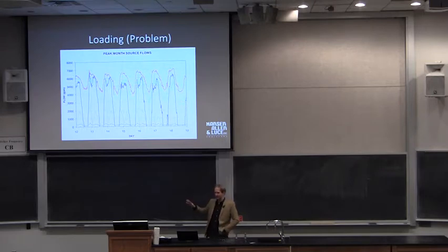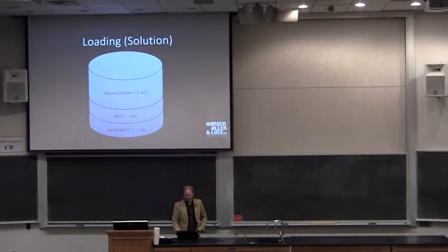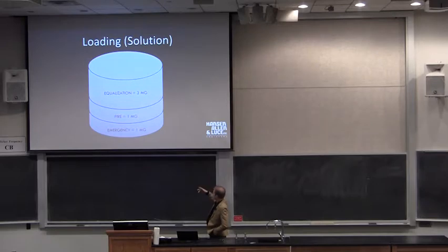So if you look around in the valley, you see lots of storage tanks, or anywhere that has water, there's usually a storage tank. Those storage tanks could be seen as batteries. If you think about it, water systems are one industry that has large batteries they can take advantage of. And so if this is a typical storage tank where you have your fire, you have your emergency storage, but most of the tank is actually designed for equalization, they call it. But that's where you can use the tank as a battery.